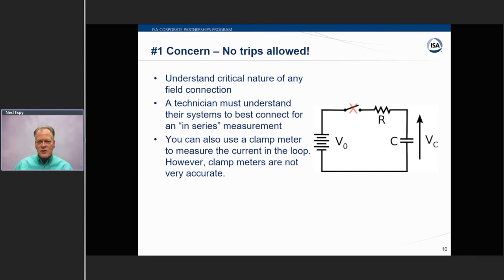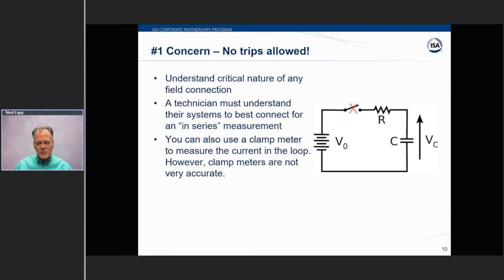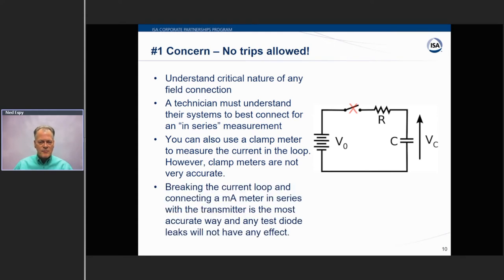When it comes time to get in series with an instrument — which is best practice — you are going to be breaking a connection and you need to understand the impact that might have. There are some alternatives, like using a clamp meter to measure current in the loop, but keep in mind these meters are not very accurate — they're more of a troubleshooting tool. Our recommendation is that breaking the current loop and connecting the milliamp meter in series is the most accurate way.